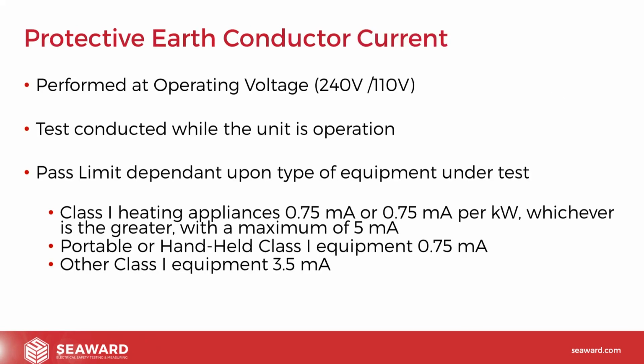So let's talk now about the protective earth conductor current, or as many of you know it, an earth leakage test. As the name suggests, the test is used to determine any leakage current that's flowing away from the insulation and into the earth cable. This flow may be coming from poorly insulated devices, flowing onto the chassis of the device, and then into the protective path, i.e. the earth cable.